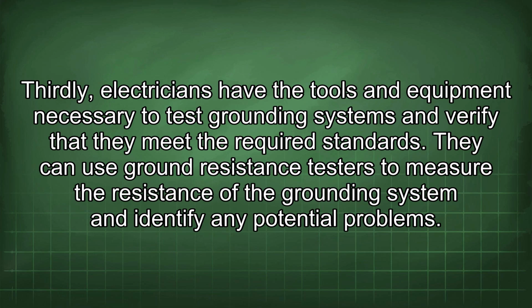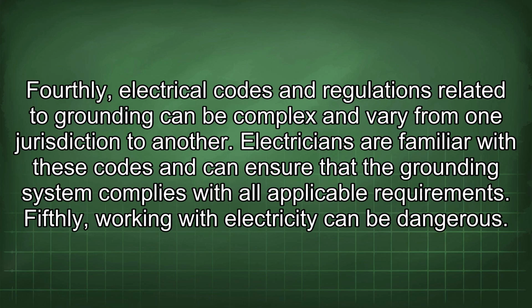Thirdly, electricians have the tools and equipment necessary to test grounding systems and verify that they meet the required standards. They can use ground resistance testers to measure the resistance of the grounding system and identify any potential problems. Fourthly, electrical codes and regulations related to grounding can be complex and vary from one jurisdiction to another. Electricians are familiar with these codes and can ensure that the grounding system complies with all applicable requirements.